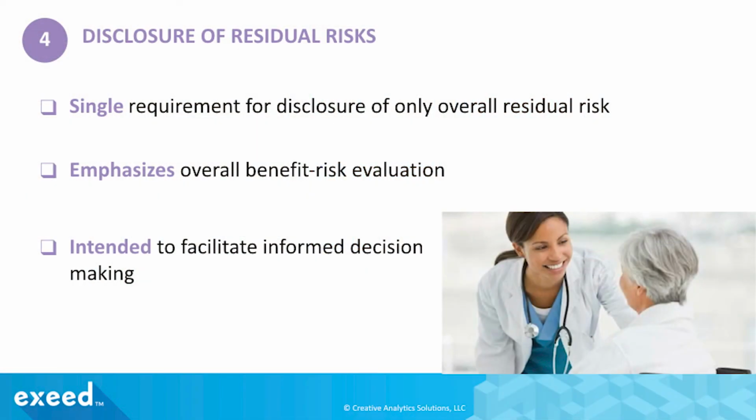There is now a little bit of a simplification in how you evaluate residual risk. Previously, you were required to do both individual residual risks and an overall residual risk. Residual risk is just leftover risk after you have implemented your risk mitigating controls. And there was a lot of confusion about how to evaluate individual residual risk and overall residual risk. Guess what?